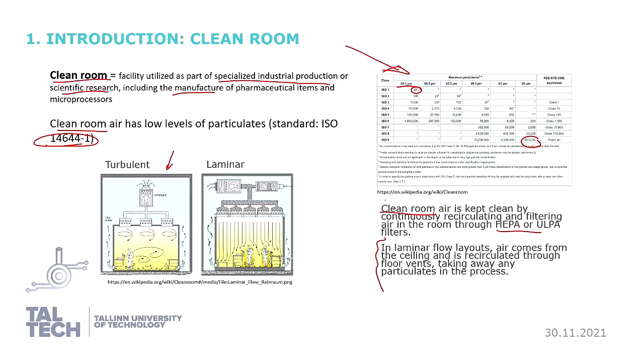Turbulent clean rooms also exist, but I have only encountered so far laminar setups, where the air is coming from vents in the ceiling and goes down with laminar flow to vents in the floor. And then they are recirculated in the supporting unit or the air system of the clean room adjacent to it, and this is filtered through industrial grade filters.